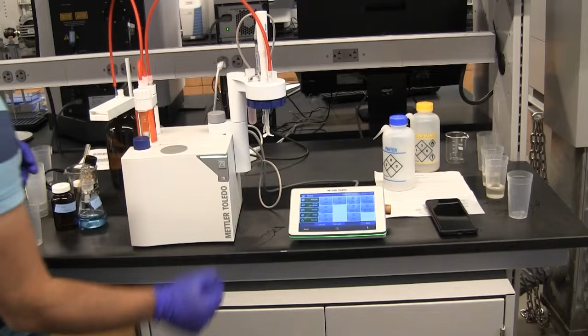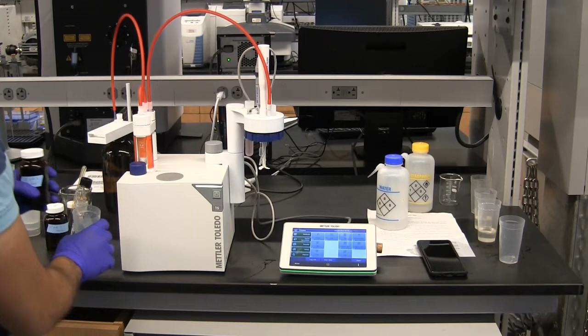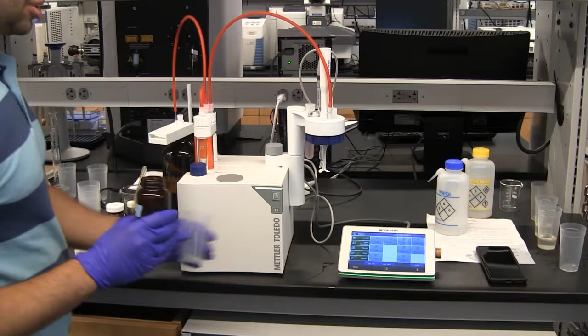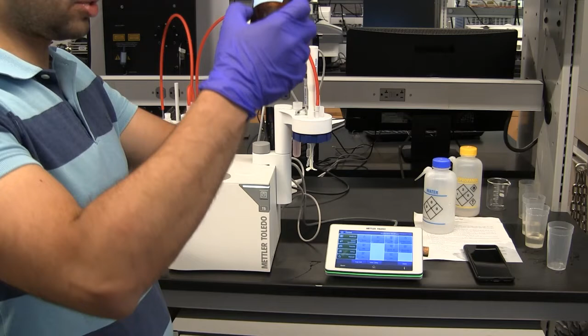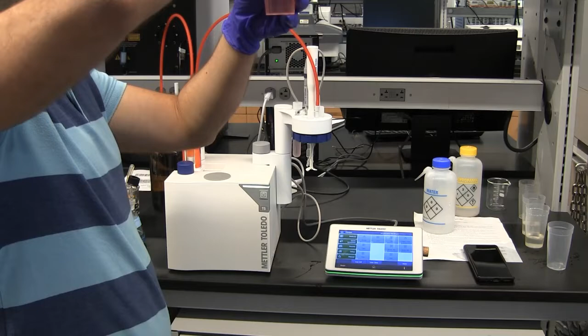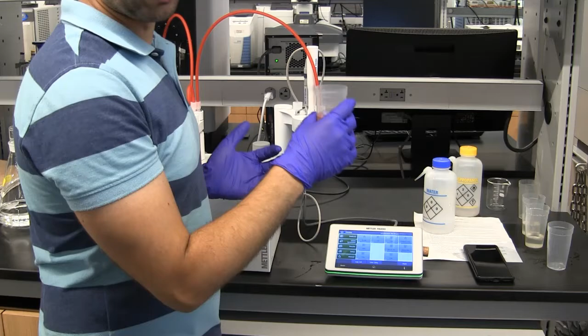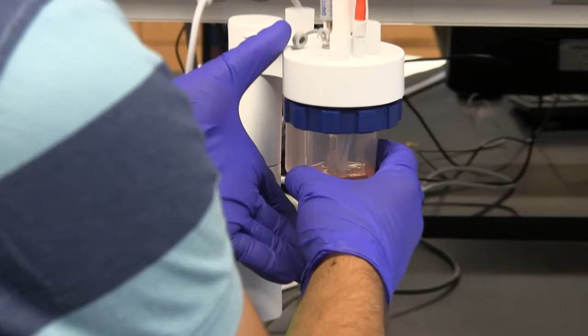So now we just do the calibration. Now we have cleaned this with water. In a cup, we will put the pH buffer of 4. We need 60 mils. Every time you put a cup in here filled with something, it has to be 60 mils. You will find that those cups are graduated, so you can just fill up to 60 mils. It shouldn't be less than 60 mils because it will not cover the pH sensor, and this is going to be a problem for your measurements later. So you put your cup back.